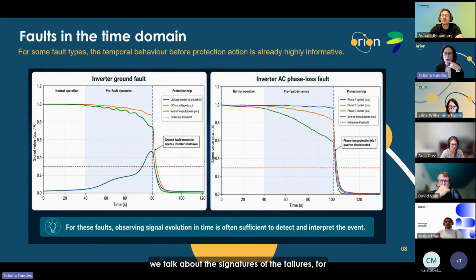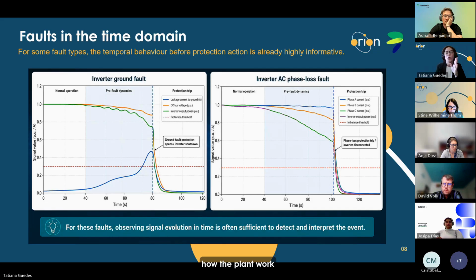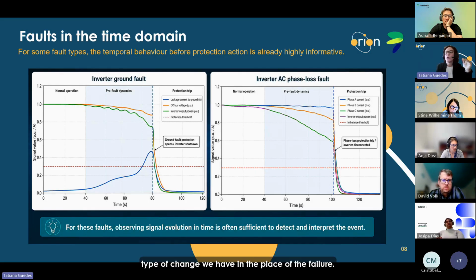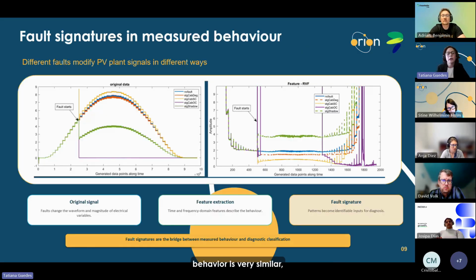When we talk about signatures of the failures, for different failures we have different scenarios. For example, we know some failures where analysis in the time domain is sufficient to detect and interpret the event. If you analyze using the time domain, we can see, before the action of protection, how the plant behaves and which type of change occurs at the location of the failure. But we have some types of failures where the behavior is very similar to a no-fault situation, or similar between different types of failures, mainly in situations of sunset and sunrise.